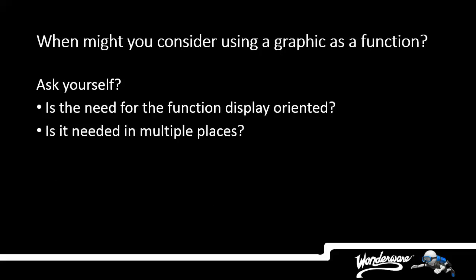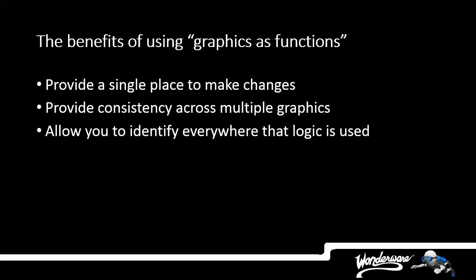When evaluating whether this technique might be useful to you or not, ask, is this function that I'm trying to perform associated with display versus non-HMI functionality such as application server, object logic, or PLC logic? And then ask, is the functionality needed in more than one graphic so management in a single location is attractive? If so, then you may have a candidate for this approach of using graphics as functions, with the benefits being to provide consistency across multiple graphics, provide a single place to make changes, and allow you to identify where that logic is used.